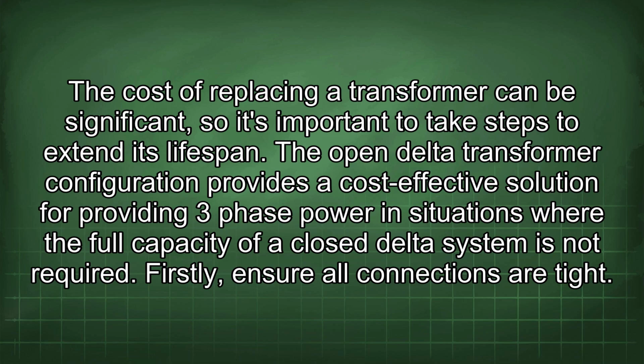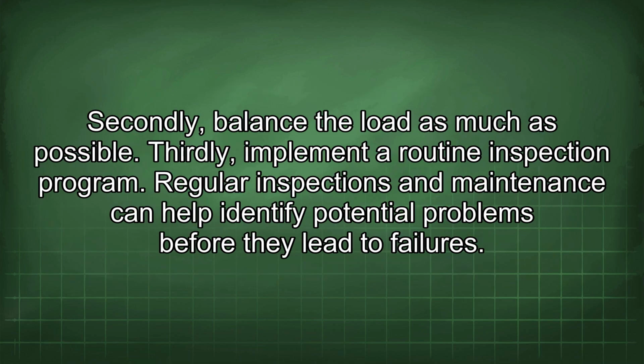The open delta transformer configuration provides a cost-effective solution for providing three-phase power in situations where the full capacity of a closed delta system is not required. Firstly, ensure all connections are tight. Secondly, balance the load as much as possible. Thirdly, implement a routine inspection program. Regular inspections and maintenance can help identify potential problems before they lead to failures.